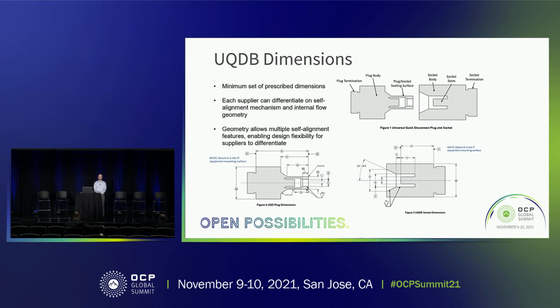system design engineers will have to understand those volumes that are necessary for keep outs and engagement and those types of things. But we did, as you can see, there's not much definition internally on these systems or on these connectors. And so each supplier can continue to differentiate on really what I think is their secret sauce in terms of the internals of this mechanism to ensure a dry break connection, disconnect, as well as to maintain a particular pressure balance or pressure flow drop within the system. And we'll talk about that on the next slide.